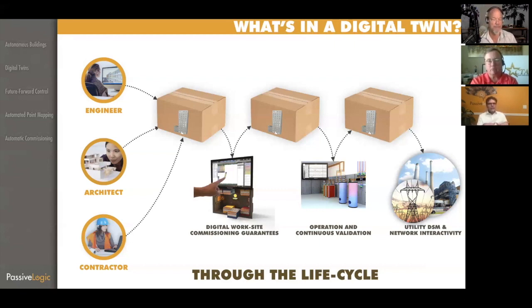So it's important to understand that when I show you the software, what we're not generating is conventional control. And there's a reason for this. We think that these conventional control ideas, like PID loops, are actually causing a lot of the pain. Let's think about the PID loop for a moment — a simple case where we have a rectangular, single-zone building with one VAV for that space. So it's as simple as it can be.